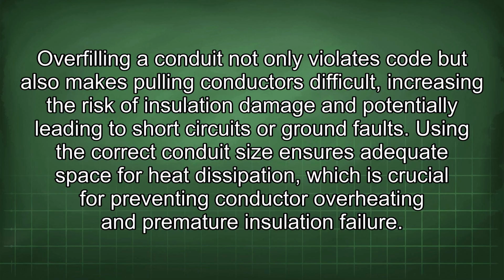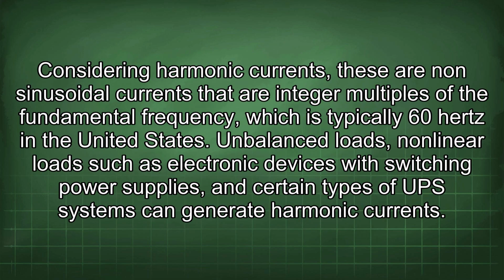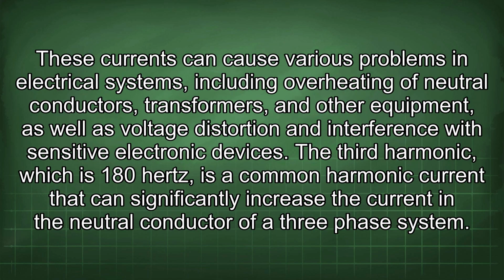Considering harmonic currents, these are non-sinusoidal currents that are integer multiples of the fundamental frequency, which is typically 60 Hz in the United States. Unbalanced loads, nonlinear loads such as electronic devices with switching power supplies, and certain types of UPS systems can generate harmonic currents. These currents can cause various problems in electrical systems, including overheating of neutral conductors, transformers, and other equipment, as well as voltage distortion and interference with sensitive electronic devices.